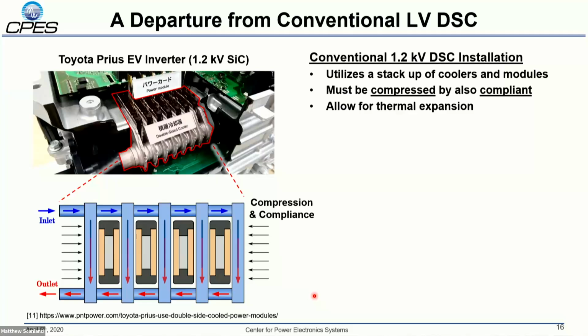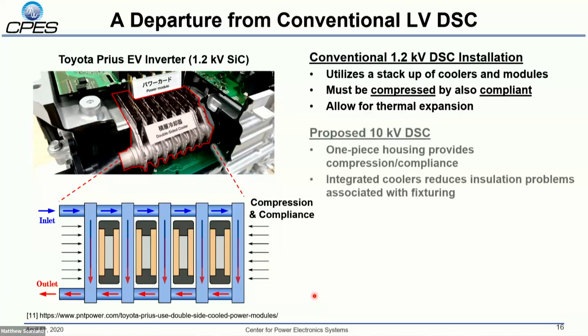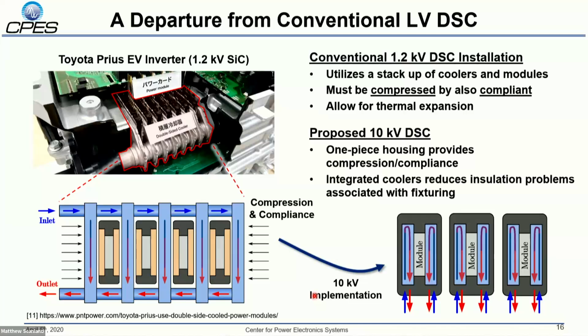So it's not just about the cooler, it's about all the fixturing around it. When we talk about creepage and clearance, we may have gotten rid of the cooler problem by integrating it, but I still have all this clamping hardware around it. Part of the strategy by integrating these coolers is also using a one-piece housing. The idea is that we no longer need compression to get a good thermal interface between the cooler and the module, because the cooler is now integrated into the module.